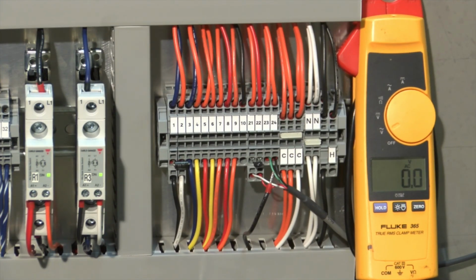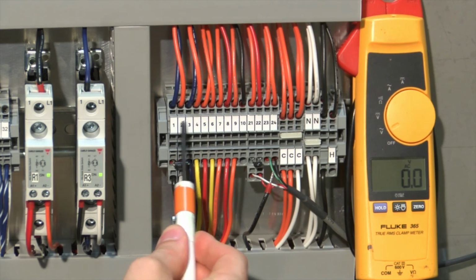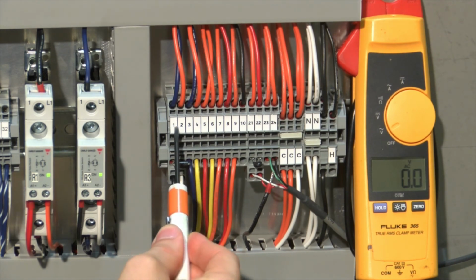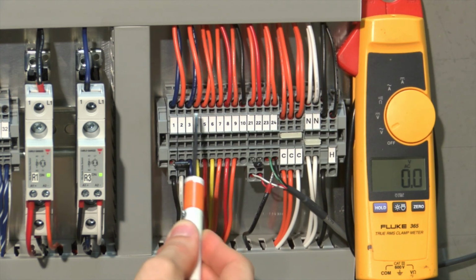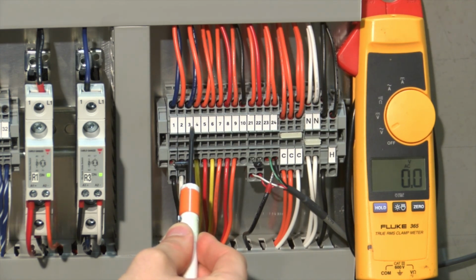The final test for transducers not operating is to verify the transducers themselves are receiving 48 volts AC. If your humidistat is calling for humidity, you verified your transformer power is good, your fuses are good, and the solid state relays are both lit, your transducer should be receiving 48 volts AC. You can verify this on terminals 1 and 2 and 3 and 4. Terminals 1 and 2 power row A, terminals 3 and 4 power row B.